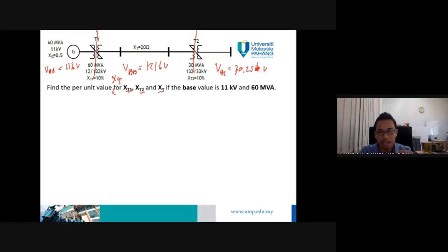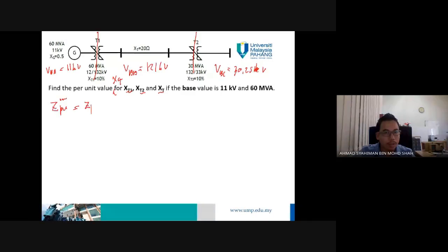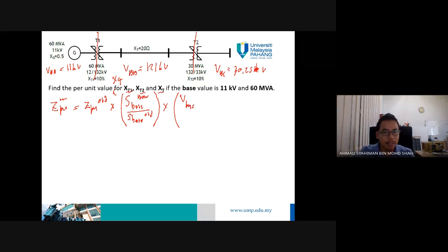So before we proceed with the reactance or impedance calculation, if you go through the earlier slides and notes up to the per unit system, there's a basis equation we call ZPU. ZPU equals ZPU old multiplied by S base new over S base old, multiplied by V base old over V base new.